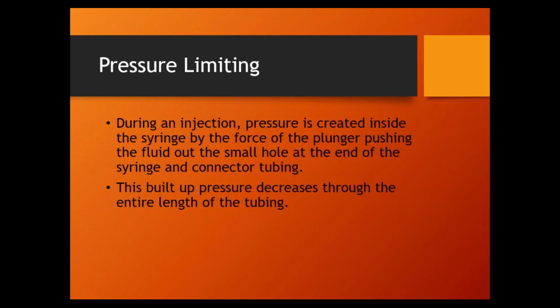All right? So no, the 1,000 PSI is in the syringe. By the time we get to the connector tubing and the catheter tubing, we are well in the low single digits. Okay? Now the fluid coming out can be coming at a very high rate, but the back pressure on the tubing in the catheter in the IV needle is very, very low. All right, so that's a big misconception. Sometimes even the operators have that.